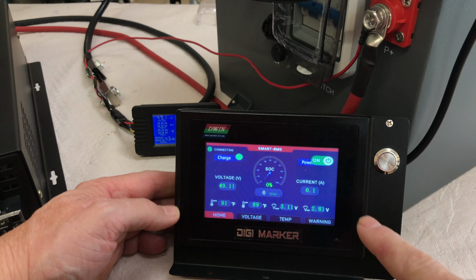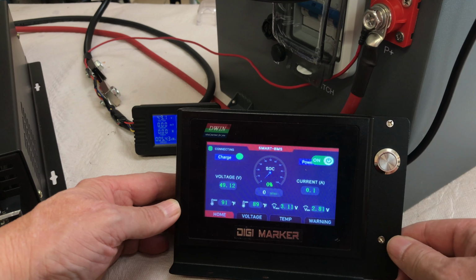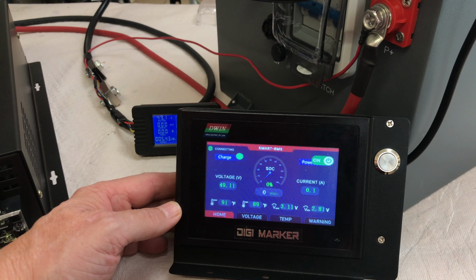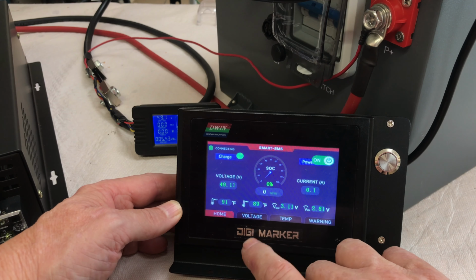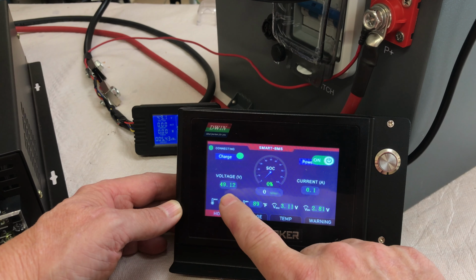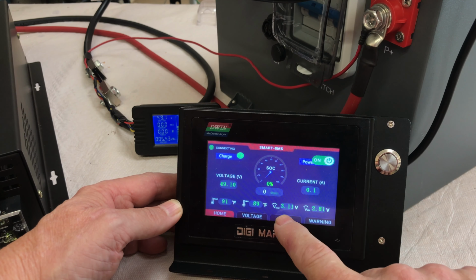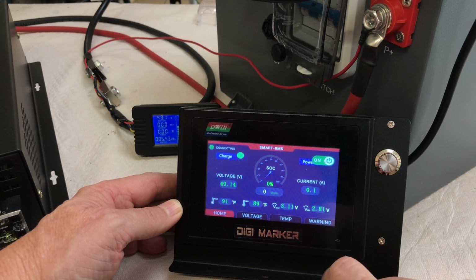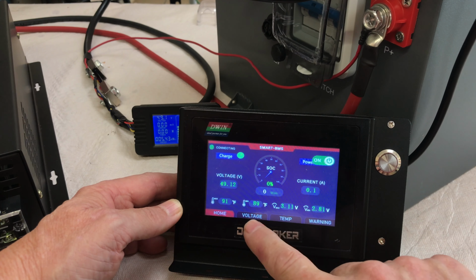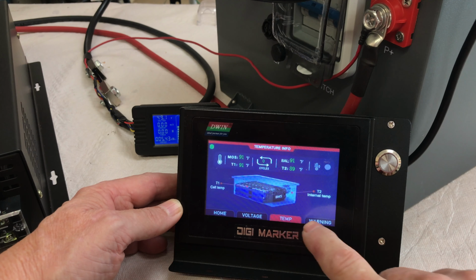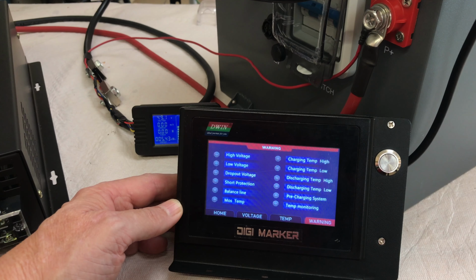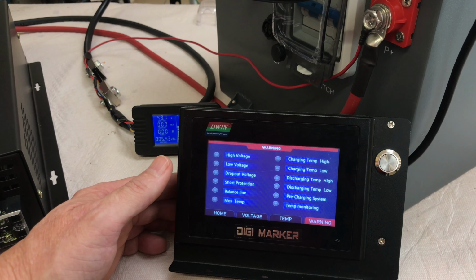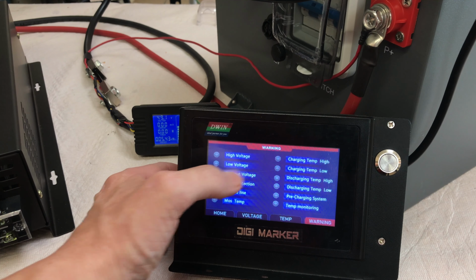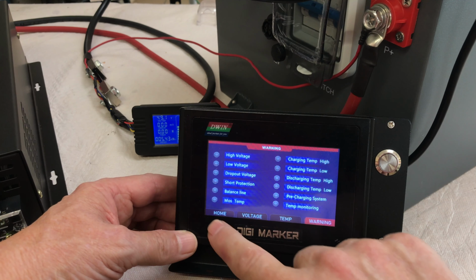Came out to check on the battery and everything was shut down. On the remote screen I was able to just hit the button and it came back on. So we've got 49.12 volts, 3.11 is the high voltage and 2.81 is the low voltage of the cells in general. I came over to the warning and it doesn't say it now, it must have sat long enough. It had the low voltage, which is what shut it down. So let's have a look at the meter.